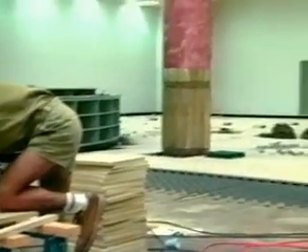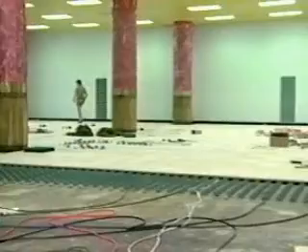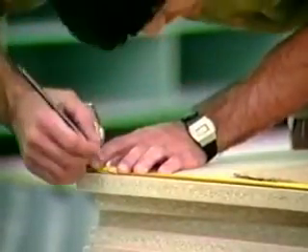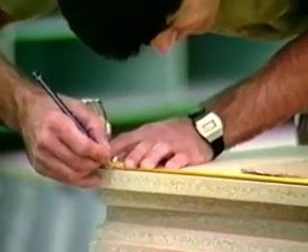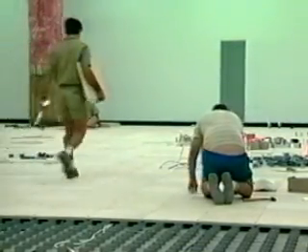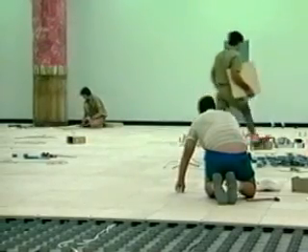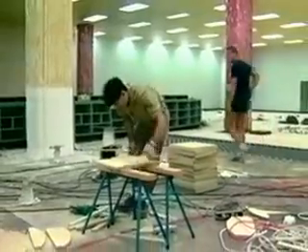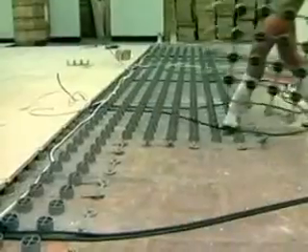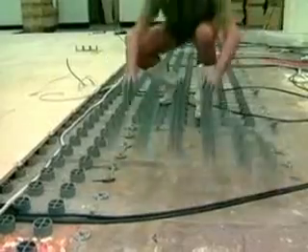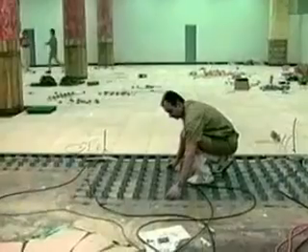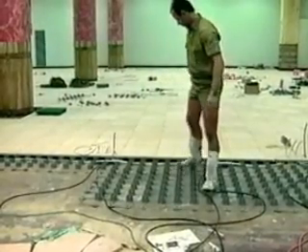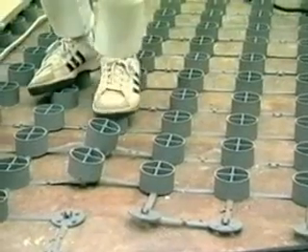Here we see Cablefloor being installed in the inquiries section of a major public utilities company. As with every installation, careful setting out is important. The installation commences from the right-hand end of the longest wall. The Cablefloor installation guide provides full details on setting out and installation. Cablefloor uses an ingenious understructure of connecting floor support modules, which are made of fire-retardant polypropylene and raise the floor height by only 60 millimeters or 2 3/8 inches.